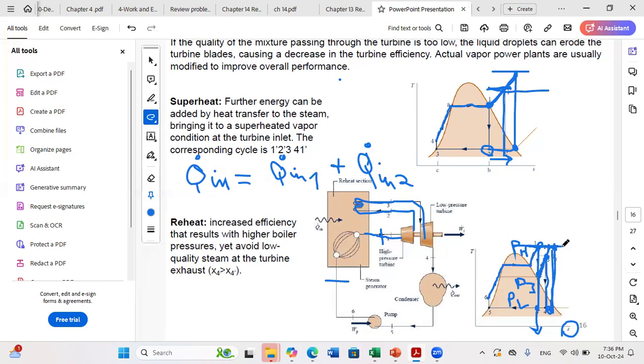So you are restricted by two conditions here: a maximum temperature not to exceed in order to avoid destruction of material properties, plus at the same time you need high quality to avoid any corrosion of your blades. So you are meeting the requirement of metallurgical temperature limits, and you are also avoiding any corrosion. So this design helped you to overcome all the disadvantages faced before.